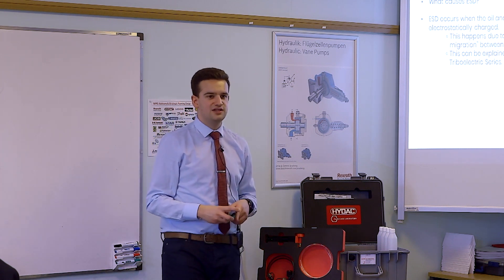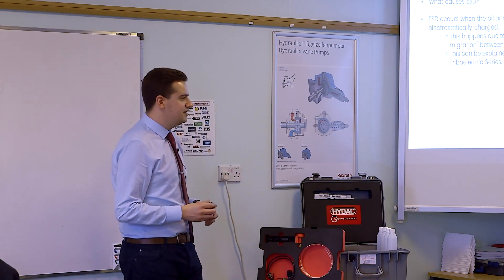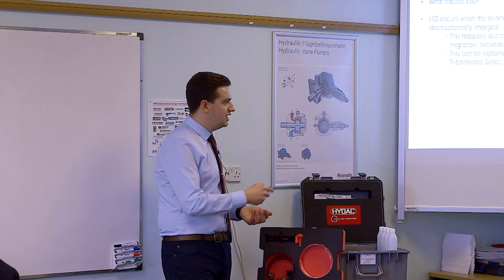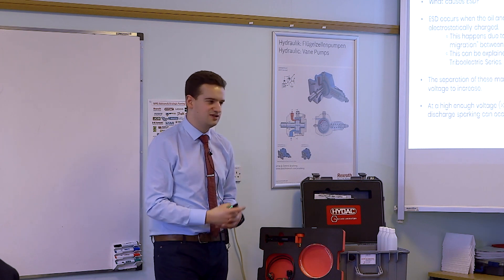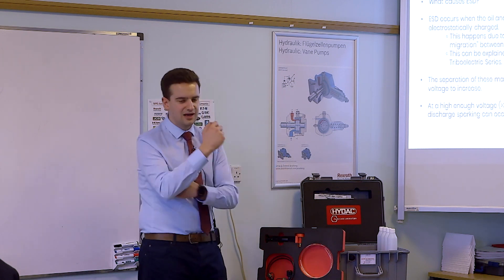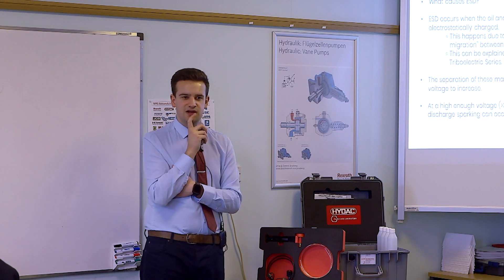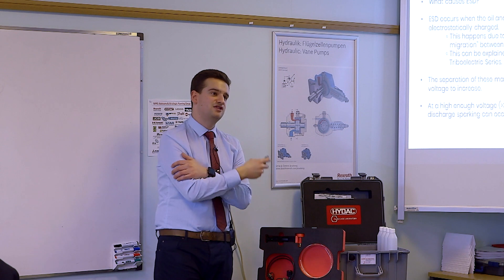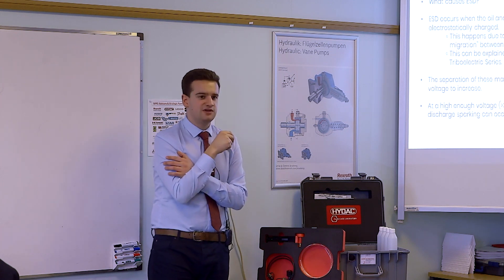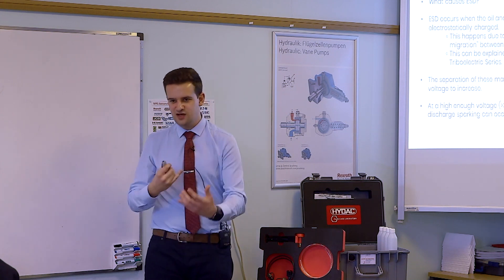I don't see as many incidences of ESD as you might expect. A lot of it is about mitigating risk. It's very clear when you take apart a filter media if there's high cases of ESD — there's a huge number of blackening and localized burn holes. We do a lot of filters and not a very large majority, maybe less than 5% or even lower, actually show signs of it, even in applications where they have low conductivity oils. That's because there are other factors: the workload at the filter itself — greater than 0.1 litre per centimetre squared per minute — and also temperature. As temperature increases, conductivity of the oil increases. So depending on the system temperature at the filter, there may be a very reduced risk of discharge.